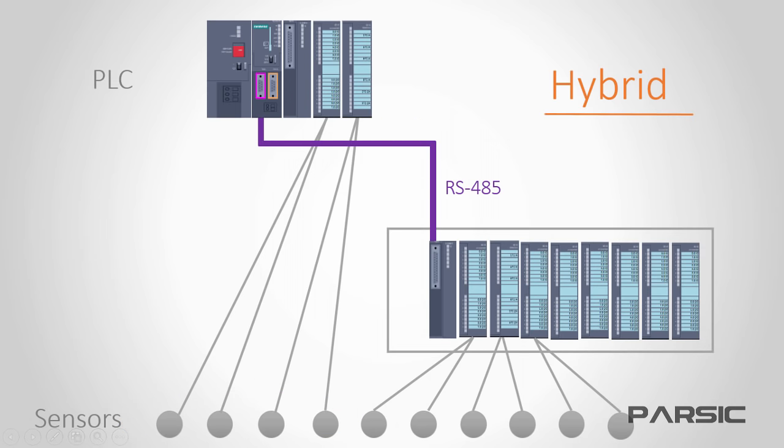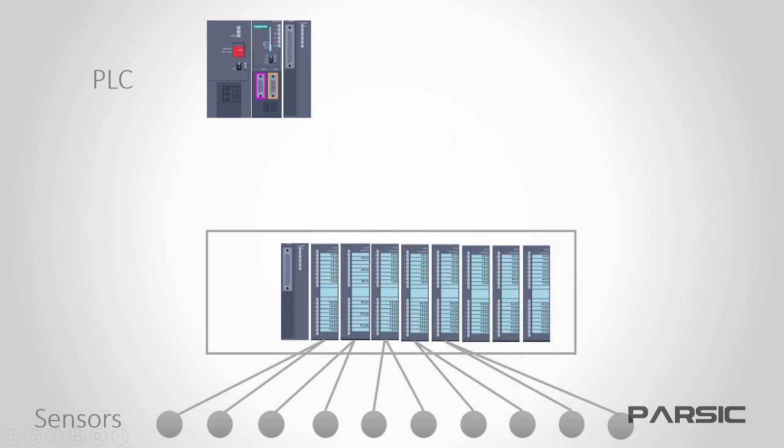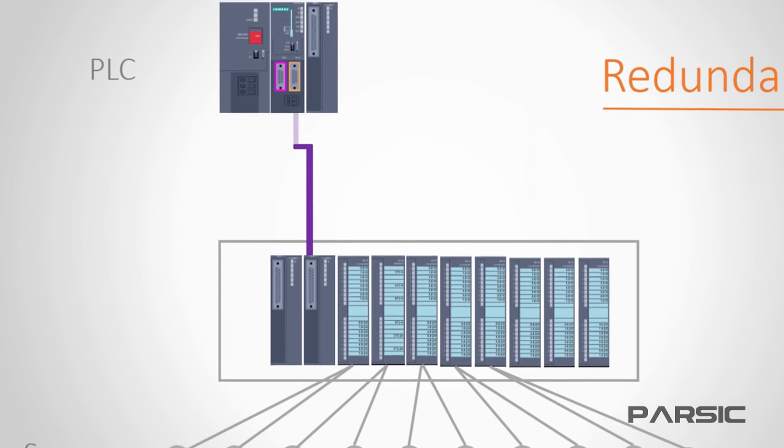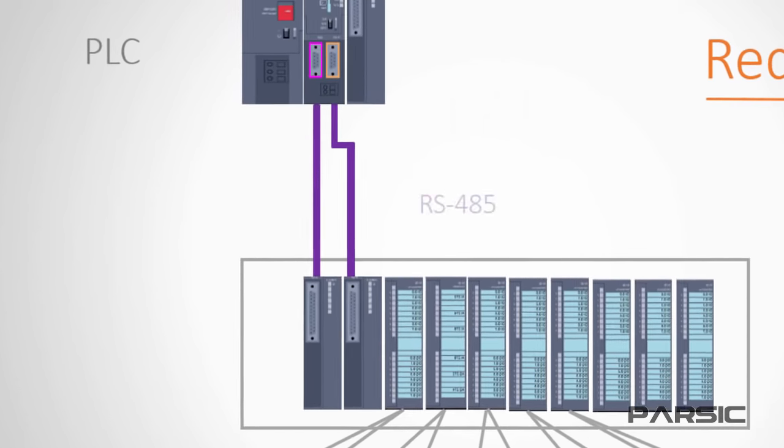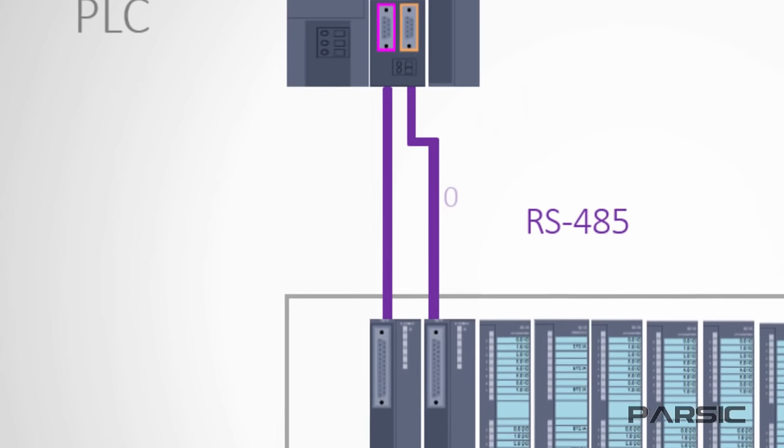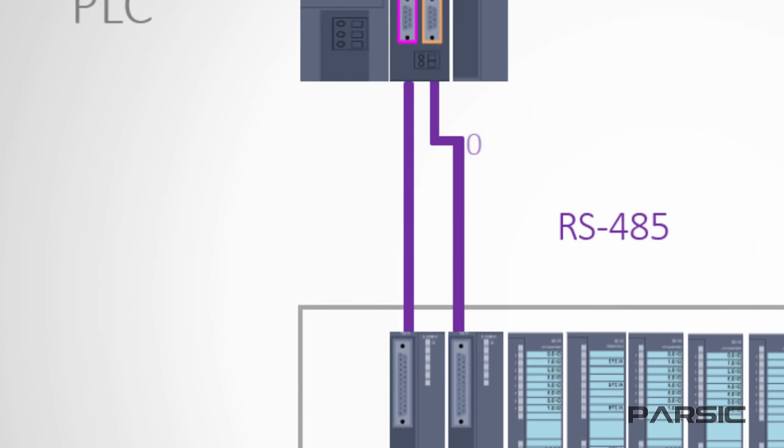Another solution is to utilize Profibus DP as a redundant network. In this method, we use two RS-485 cables to connect the remote IOs to the PLC. In this configuration, if the main cable goes down, the data transfer can be switched to the reserve cable with no problems.